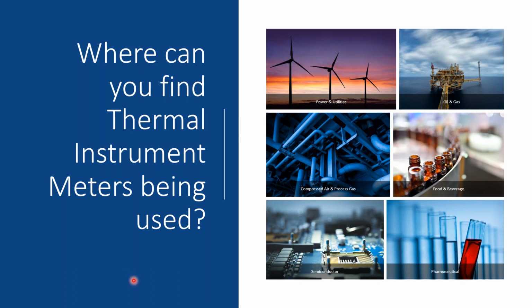Ray, we have one question regarding water. Does there need to be a level of conductivity like you would need in a mag meter for thermal mass measurement? Actually, that's one of the advantages of using thermal mass. Thermal mass doesn't care about conductivity. We just care about the thermal transfer, the heat. So whether it's DI water, regular water, or water for injection, we don't need conductivity like a mag meter does. Where mag meters have some advantages in other areas, that's where we have an advantage in that we don't need that conductivity.